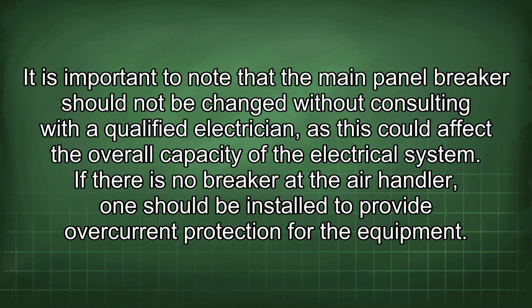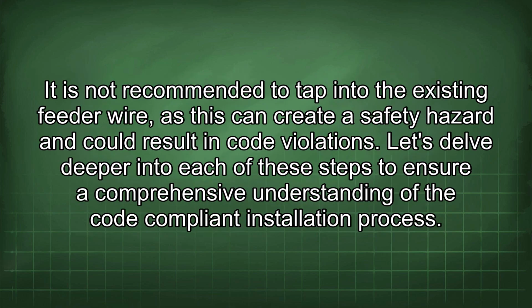It is important to note that the main panel breaker should not be changed without consulting with a qualified electrician, as this could affect the overall capacity of the electrical system. If there is no breaker at the air handler, one should be installed to provide overcurrent protection for the equipment. It is not recommended to tap into the existing feeder wire, as this can create a safety hazard and could result in code violations.